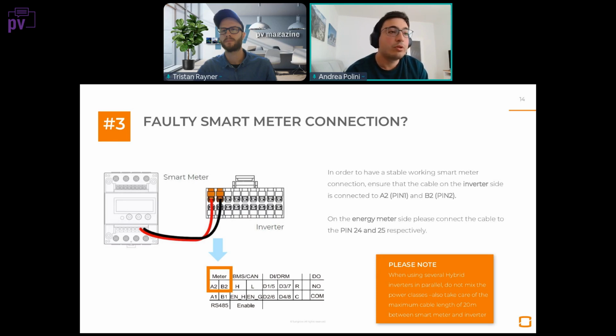If it's impossible to use only 20 meters of cable because the installation is too far away, we recommend to use a shielded cable, a shielded RS485 cable. Even audio cable is quite good, like a loudspeaker cable works quite fine, we have found.